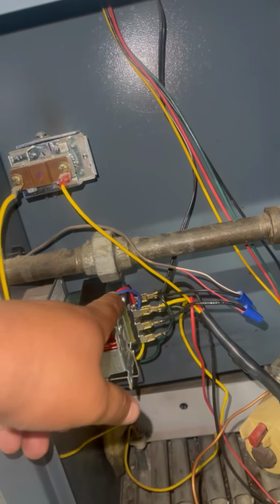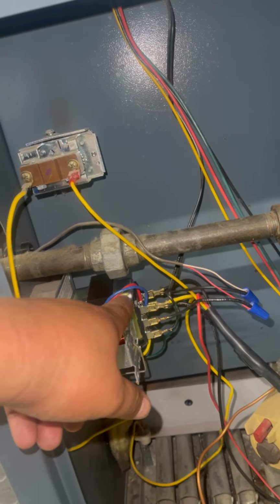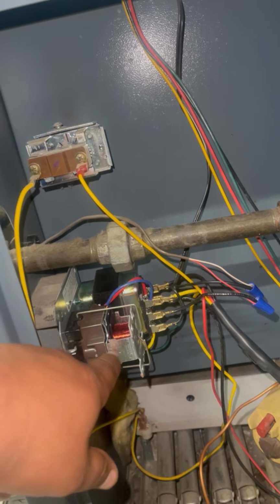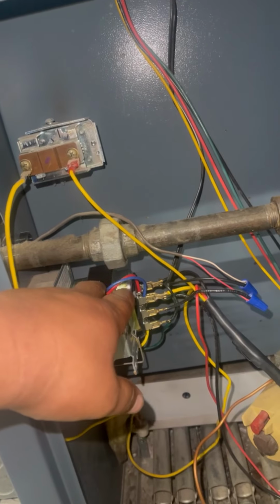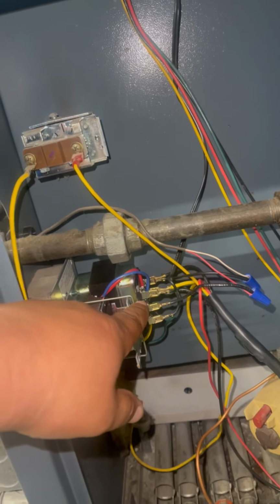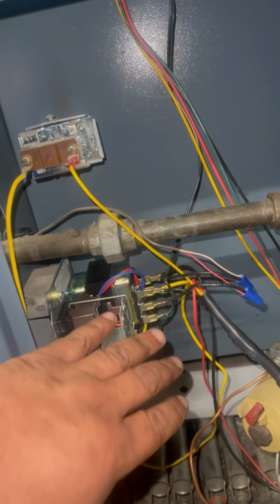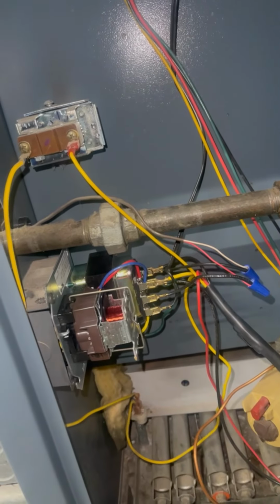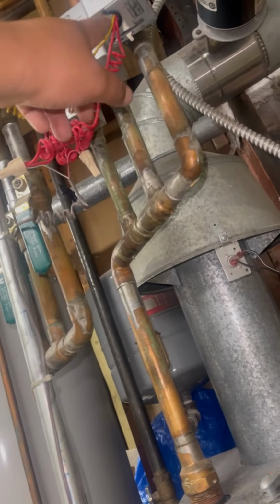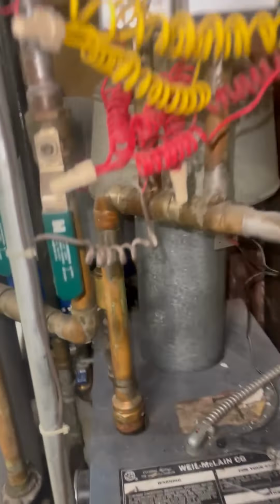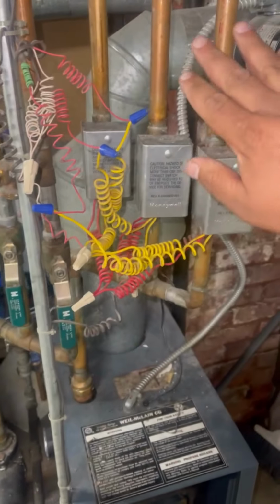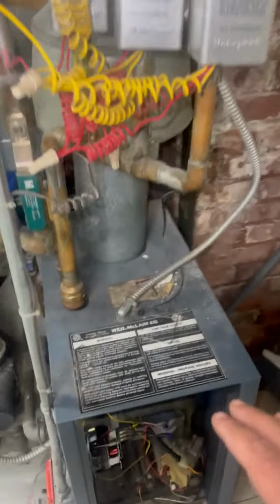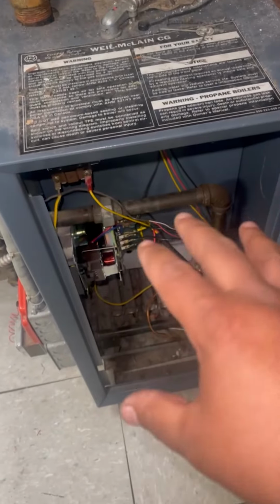So the actual transformer on the old relay was good, but the relay was actually bad. But I'm gonna get to that in just a moment. So I got 24 volts. I got power. I established this power. But what I did notice is that the zone valves are open. So we got 3 zones. These 2 zones right here are open. One is not calling. So I know this power, I know it's separate. So basically, I eliminated the zone valves on one end. So I know the problem is actually somewhere inside the boiler.